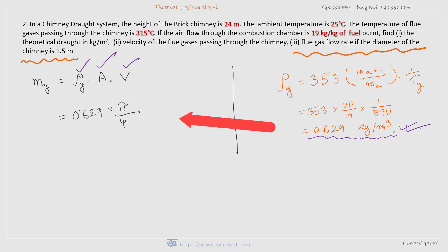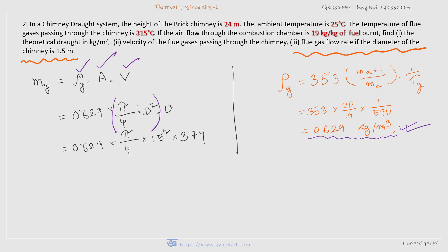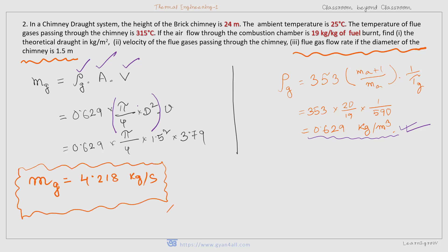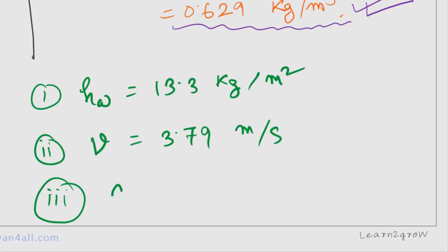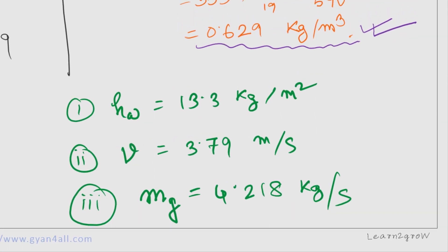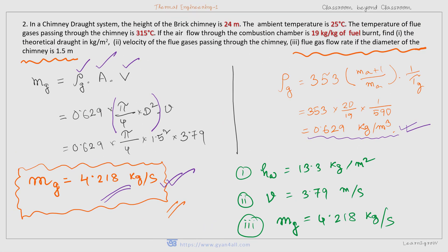Putting the value of rho_g, the cross-sectional area pi by 4 d squared where d is 1.5 meters, and V as velocity — 1.5 squared into 3.79 — we get the mass flow rate, or flue gas flow rate, equal to 4.218 kg per second. So we have solved: number one, the pressure difference in kg per meter squared; number two, the velocity of flue gas through the chimney; and number three, the mass flow rate through that chimney. Thank you for watching.